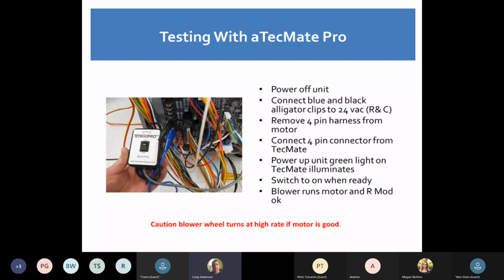That TecMate Pro is going to have an on and an off switch. It's going to light up green, and that's going to tell you we're ready to go. Flick the switch to on. If that motor turns on, that's telling us that the control is working, the motor is working.